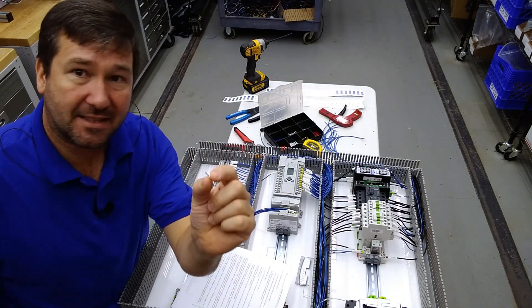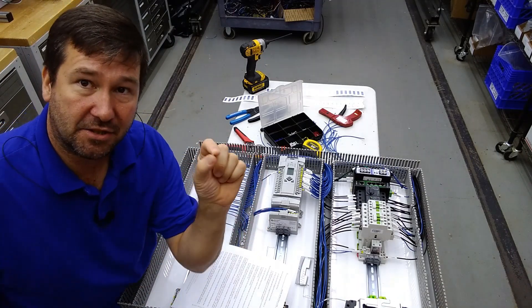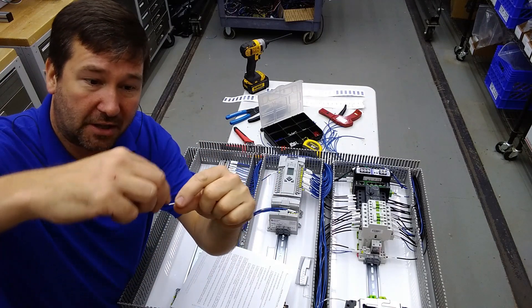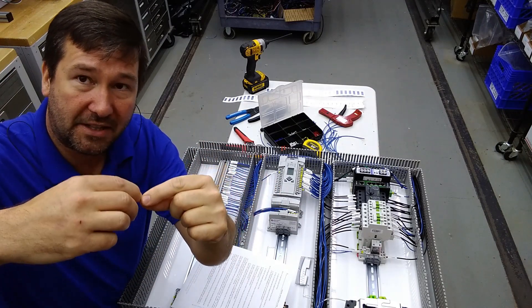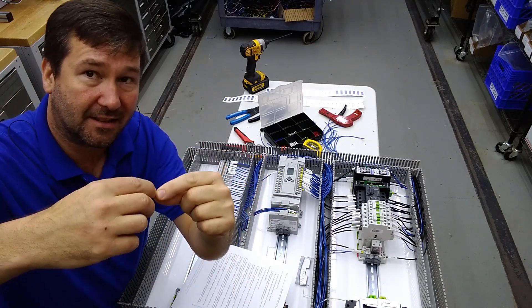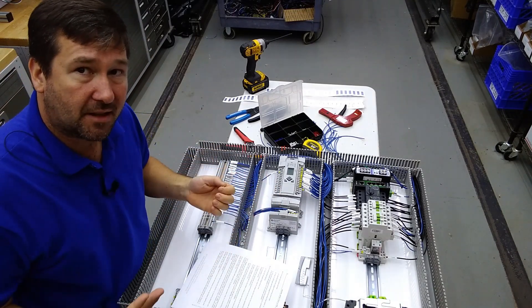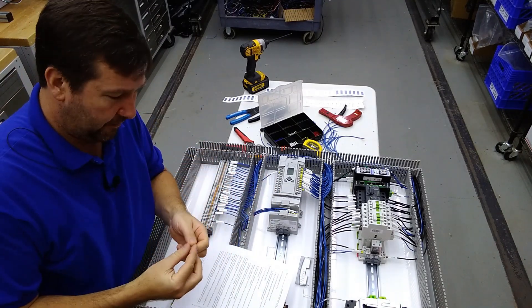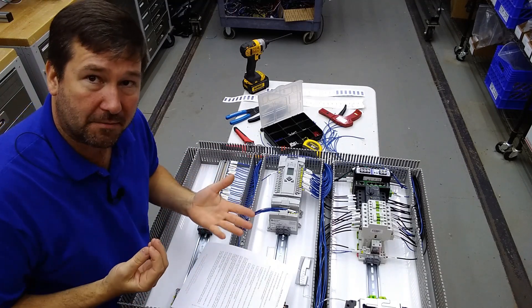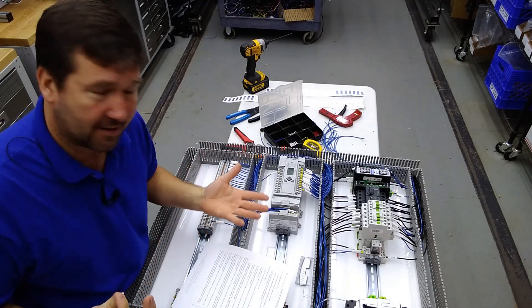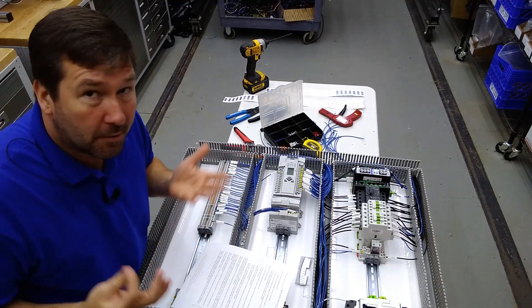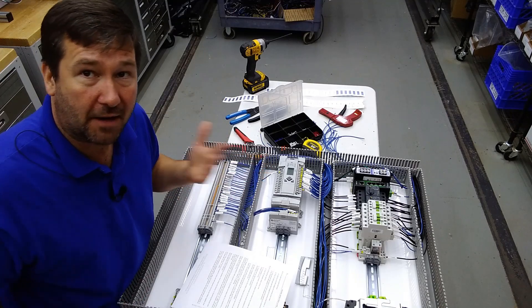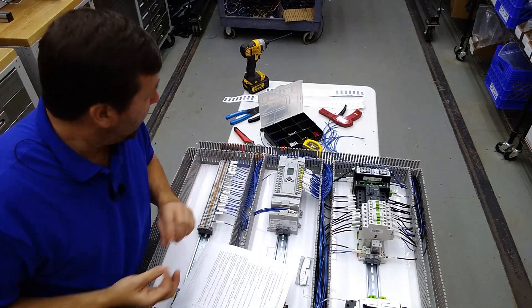The biggest thing about the insulated end is you stick them in too far, you can end up clamping down on the insulation. I think that's more of an install issue and I see a lot of problems with the uninsulated ones, but really as far as UL they're fine with either way.